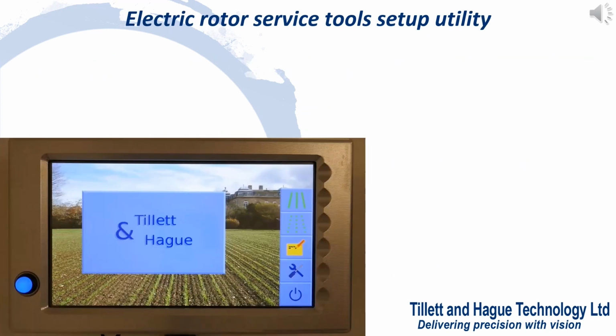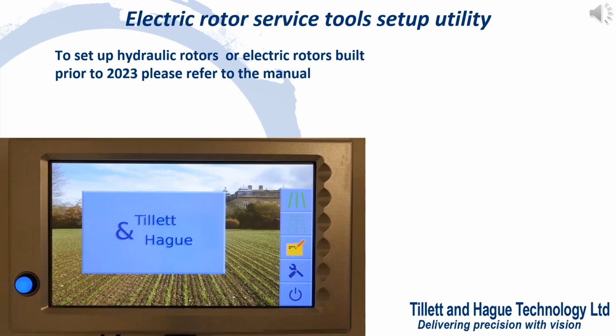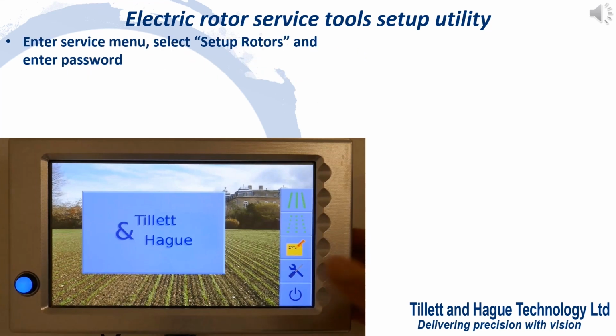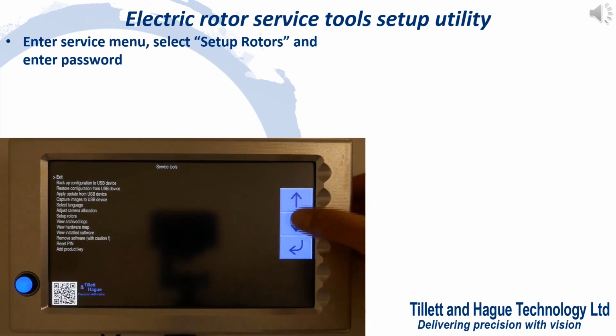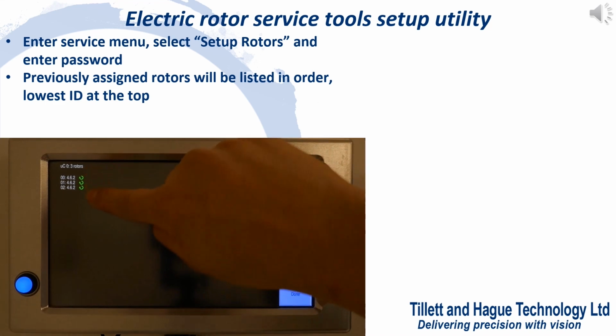So now we're going to talk specifically about setting up electrically driven rotors. Please consult the manual for instructions relating to the hydraulic equivalent or electric rotor machines built prior to 2023 that have a slightly different procedure based on setting dip switches. Start by going into the service menu and selecting Setup Rotors and entering the password. If rotors have already been identified, they will be listed here in order from lowest ID at the top of the screen to highest ID at the bottom.